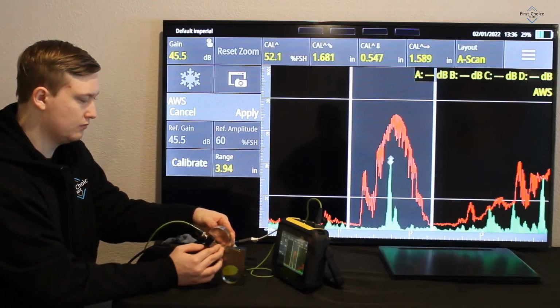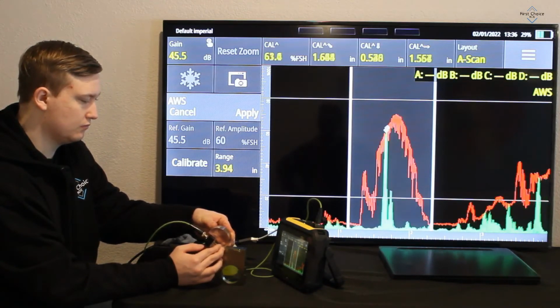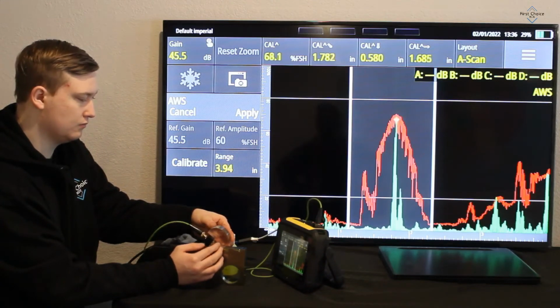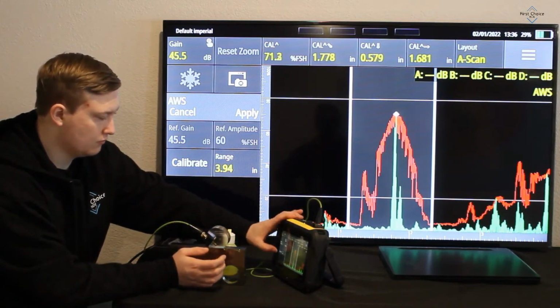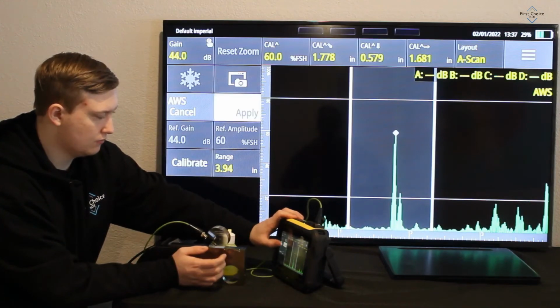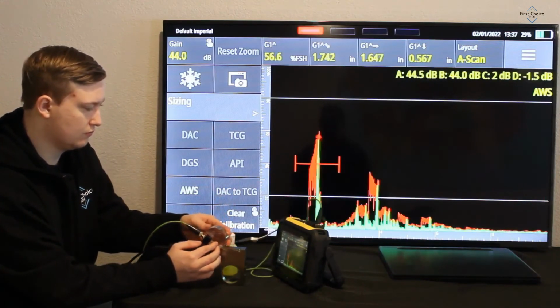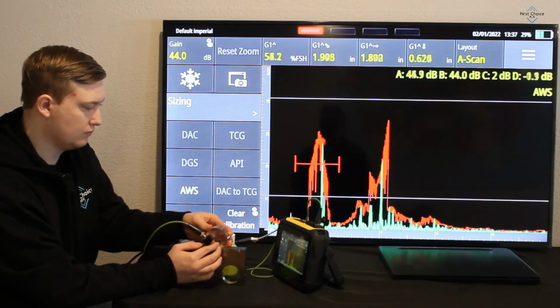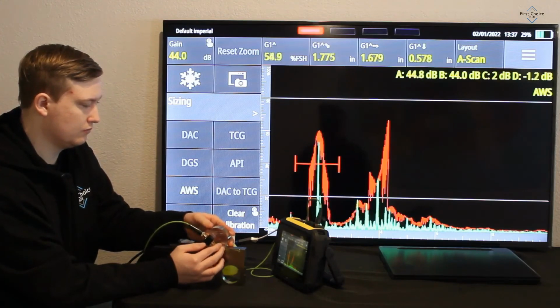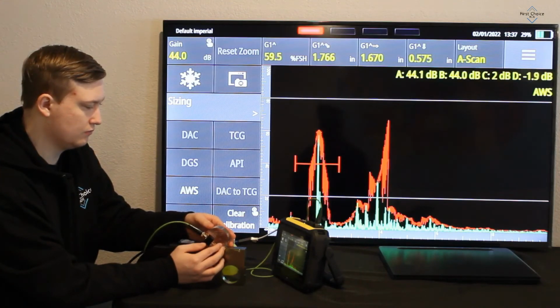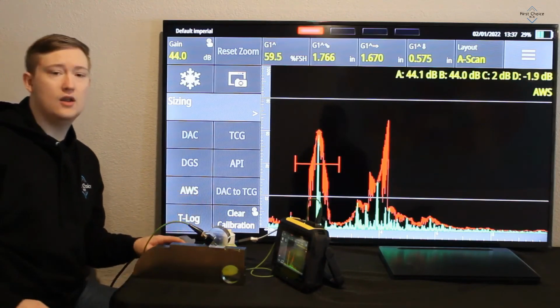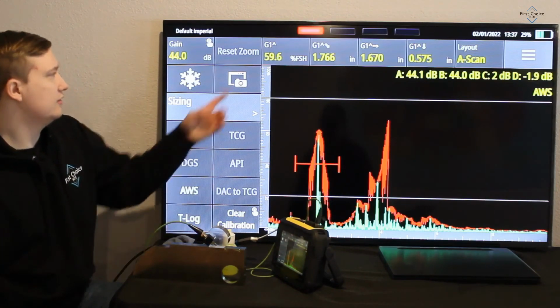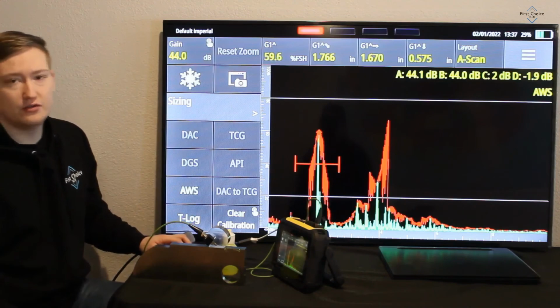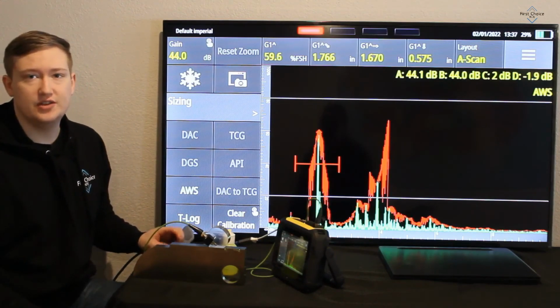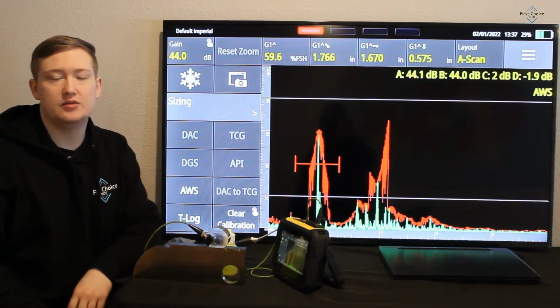So I'm going ahead and doing the same step, looking for the peak on the envelope. And you see a peak being developed right around there, right there. So I'll go ahead and press calibrate now. Apply. Now I'll go ahead and peak it out again. All right, and as you can see there, I have a 60% screen height at 44 decibels. That's going to be my sensitivity. And that's going to conclude the AWS calibration.